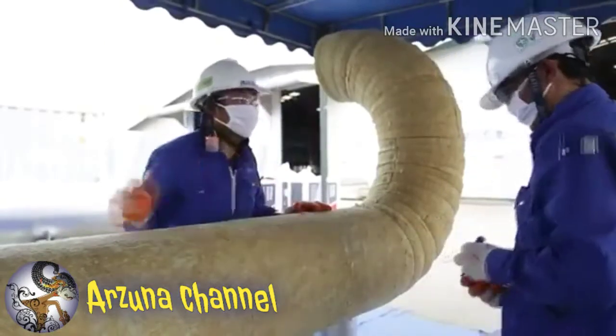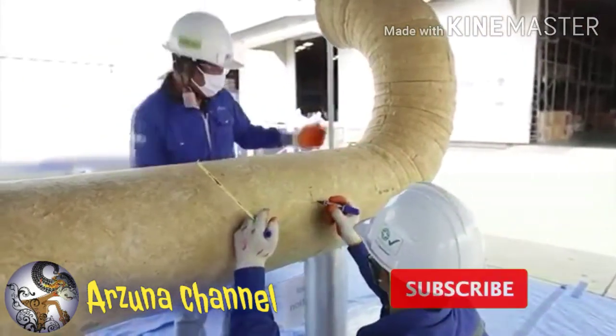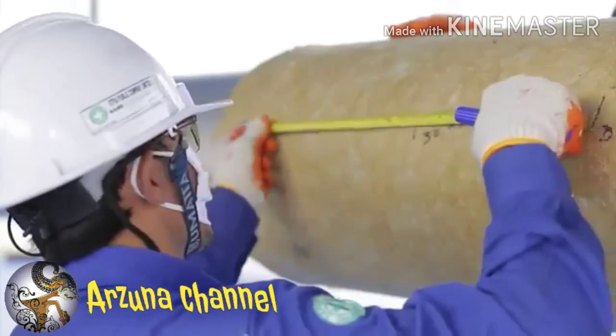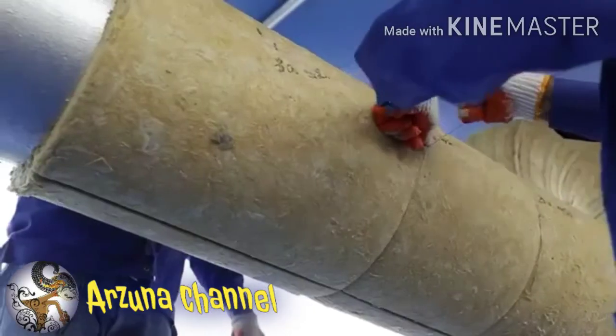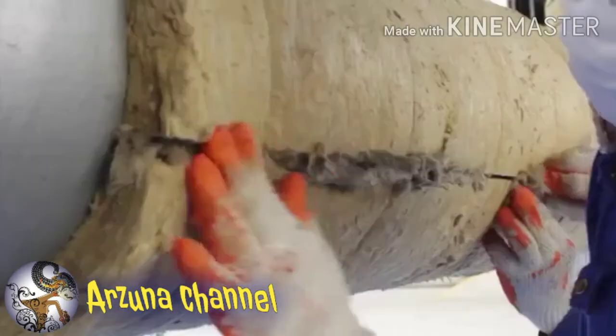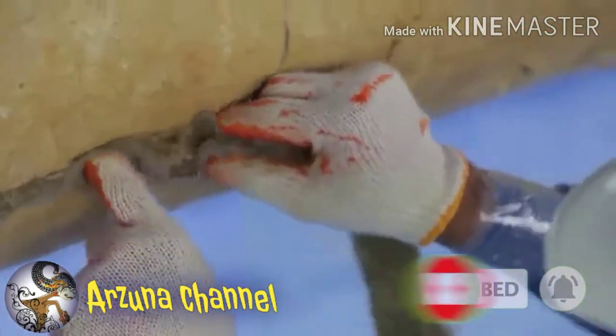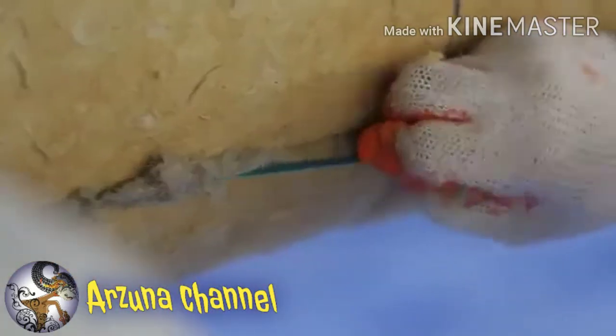While installing the Rockwool pipe section on the straight pipe, 10 cm should be left from the elbow in order to fasten the insulation with wire or bands according to the installation standard for industrial insulation on pipe. Continue marking points at 30 cm from the first point and continue until the end of the pipe according to the installation standard, to fasten the Rockwool pipe section firmly to the pipe with steel bands or wire. In some cases, there are gaps between insulation joints. Joints between the individual segments of insulation are plugged tightly with loose Rockwool insulation in order to avoid thermal bridges.